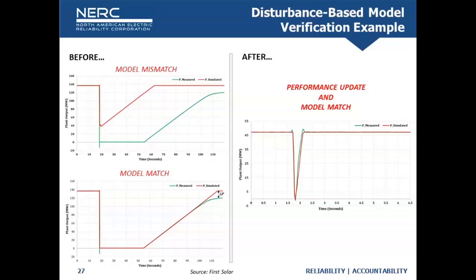That response is really bad. We saw a lot of resources out there like this. First Solar did a tremendous job of monitoring their resources, ensuring not only that the model matches reality, but that the unit performs in a way that supports grid reliability. We're seeing a growing number of success stories where changes were made because settings had been implemented into inverter-based resources with little knowledge of what actually supports grid reliability. If every resource drops off and doesn't provide power for 35 seconds, the lights go out. We all understand that in transmission planning—the lights go out if you cease injecting current for even half a second to a second, depending on your interconnection. So 35 seconds is an eternity to a stability engineer.